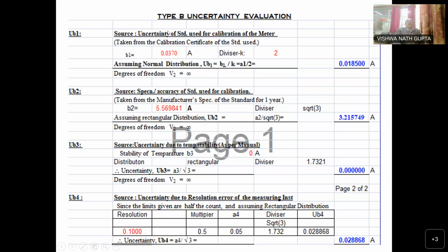So here we have incorporated it, and here the divisor k means coverage factor. Same thing, sir: this uncertainty is a very big and elaborate chapter. A 4-day training is given on uncertainty alone by reputed institutes, sometimes by the ERTL, IDMI, or NABL also, on the topic of uncertainty. So assuming normal distribution, we just have to illustrate degrees of freedom for B1. Now this one is the UB1, the uncertainty of the standard used for the calibration of the meter. It has come here.